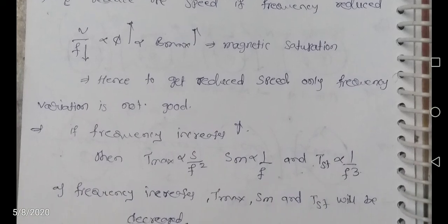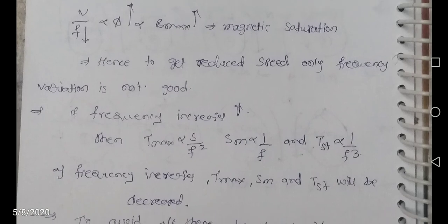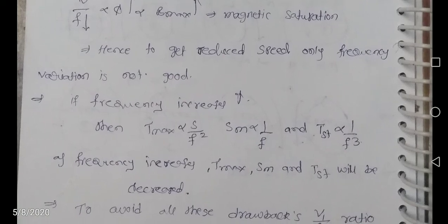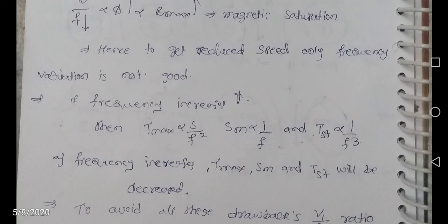If frequency is increasing, then maximum torque T maximum is decreasing, and slip at maximum torque will decrease. Starting torque Tst is proportional to 1 by F cube. With increasing frequency, starting torque also decreases slightly. So if frequency increases, maximum torque, slip at maximum torque and starting torque will be decreased.